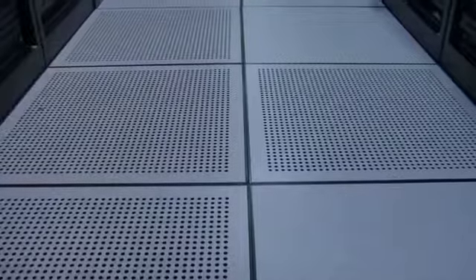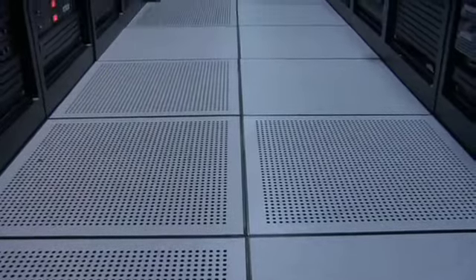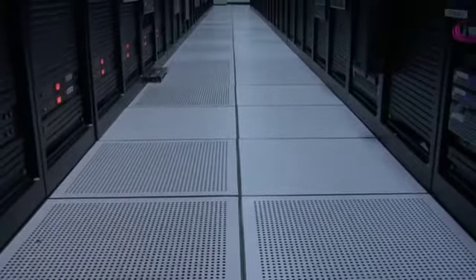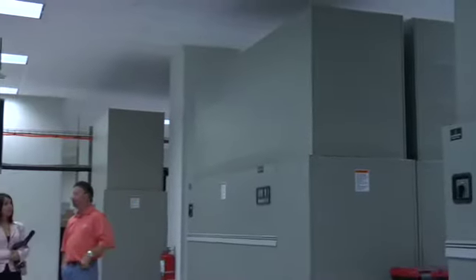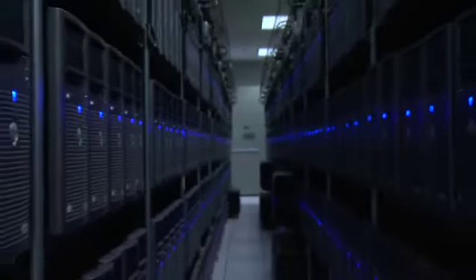That's pretty big. We've done a lot of things on the cooling efficiency of our data centers. We've done a lot of work with blanking plates, and a lot of temperature measurement in the data center to try to make it more even across the data center. We've actually raised the temperatures in our data center a little bit, towards the top of the ASHRAE standard. It's mainly just making sure the cold air is getting to the fronts of the servers and nowhere else in the room.